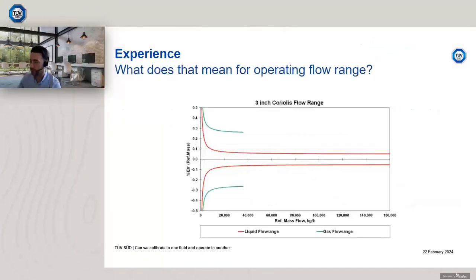So on the next slide, I have a 3 inch Coriolis meter, and I have the nominal flow range for liquid and the nominal flow range for gas. So liquid in this case is the red and the gas is green. This is a meter specification, so I've got on the y-axis the percentage error, if you can imagine, for this device, and on the x-axis the reference mass flow in kilograms per hour.